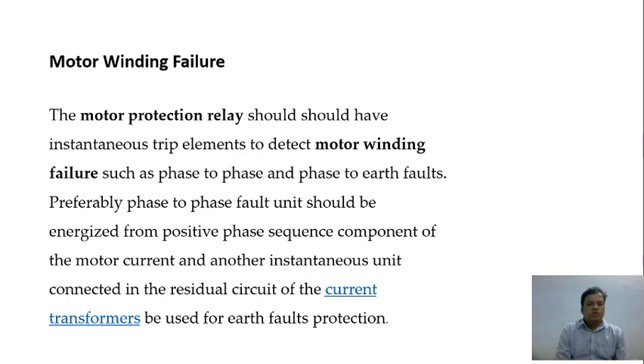Preferably, the phase-to-phase fault unit should be energized from the positive phase sequence component of the motor current, and another instantaneous unit connected in the residual circuit of the current transformers should be used for earth fault protection. I think this is the method used to protect against motor winding failure. So the phase-to-phase fault unit is energized from the positive sequence component of the motor current, and another instantaneous unit connected in the residual circuit of the current transformers is used for earth fault protection. If these are followed, then we can avoid motor winding failure.